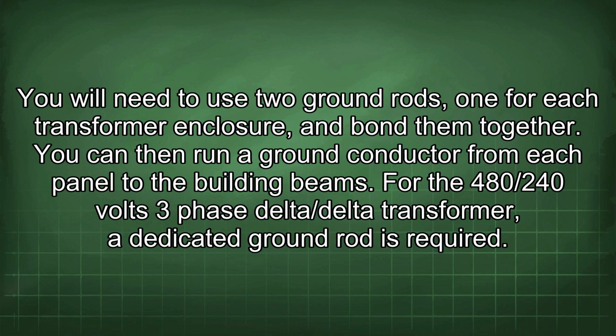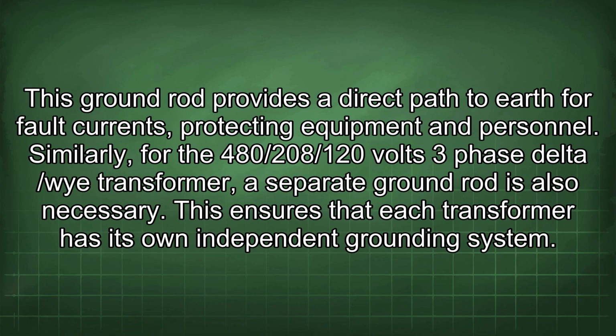For the 480/240 volts 3-phase delta/delta transformer, a dedicated ground rod is required. This ground rod provides a direct path to earth for fault currents, protecting equipment and personnel. Similarly, for the 480/208/120 volts 3-phase delta/Y transformer, a separate ground rod is also necessary. This ensures that each transformer has its own independent grounding system.